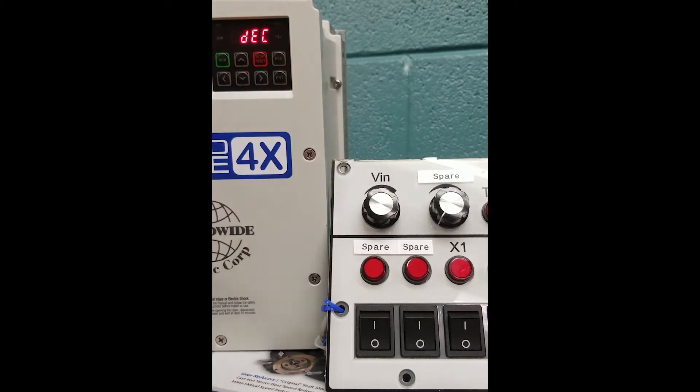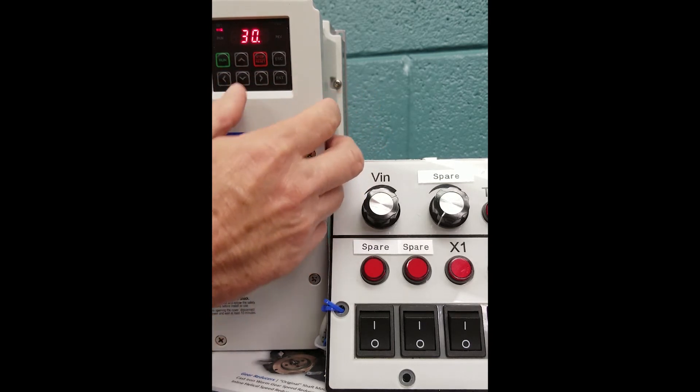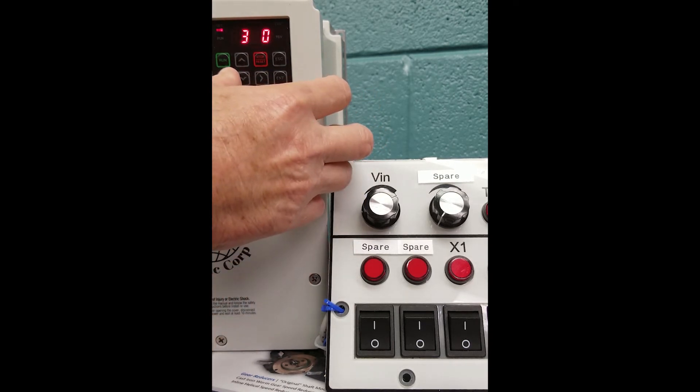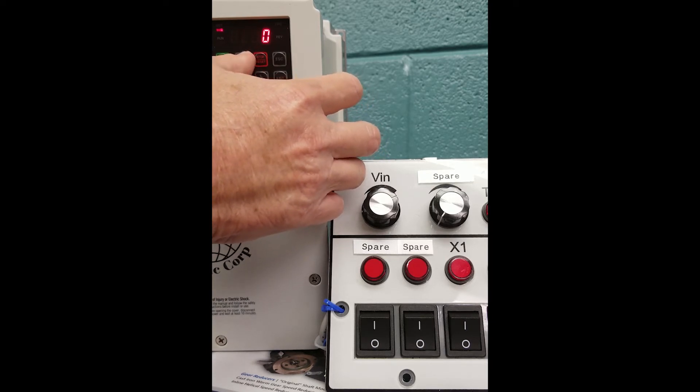We're going to use the up arrow again to hit the DEC for deceleration, enter to enter in the parameter. This unit is factory default at 30 seconds. We're going to set it at a 4 second deceleration time, again using our keypad to make these changes.